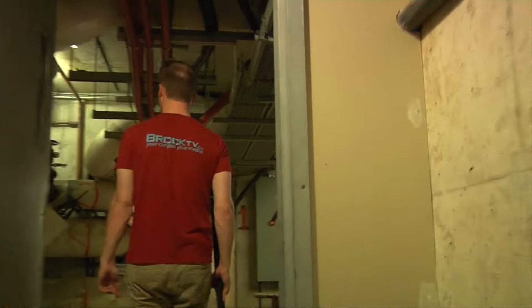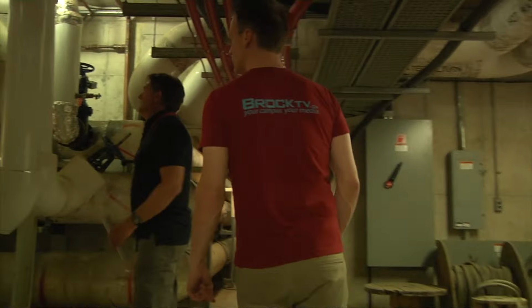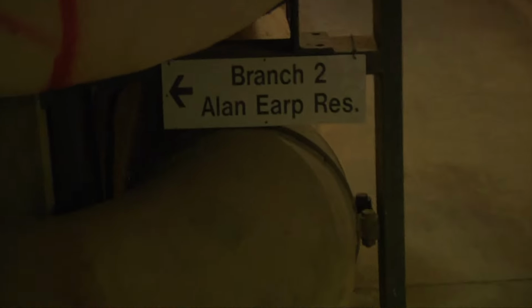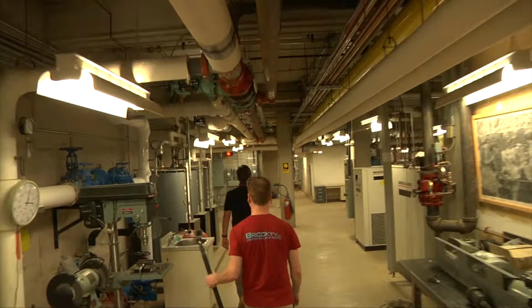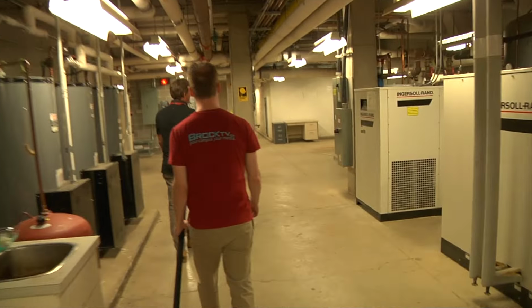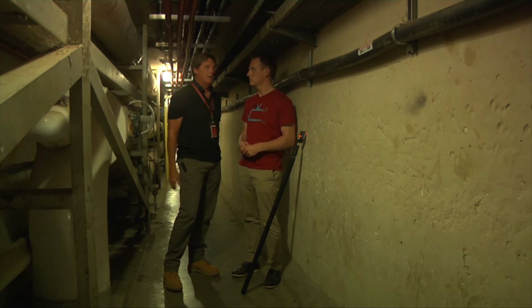Along with that is all of our feeders for all the electrical power going out to the campus. We transfer 13,800 volts. Each one of these will go to a substation in each building where it's transformed down to usable voltage, right down to 120 volts for a lighting circuit.